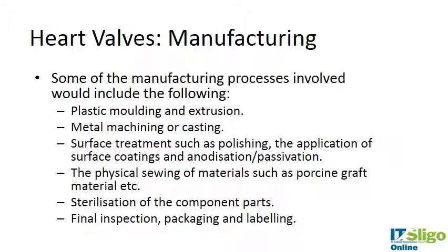In terms of manufacturing: plastic parts can be molded and extruded; metal machining or casting is used for the discs, which then need to be polished. Surface coatings such as pyrolytic carbon are deposited using plasma spray or chemical vapor deposition. Anodization and passivation are important to prevent corrosion. The porcine graft material is physically sewn. Component parts are sterilized — mechanical valves using ethylene oxide, e-beam, or gamma ray; for porcine grafts, steam sterilization may be used. Then final inspection, packaging, and labeling follow.